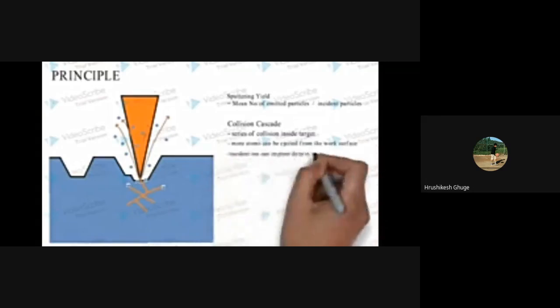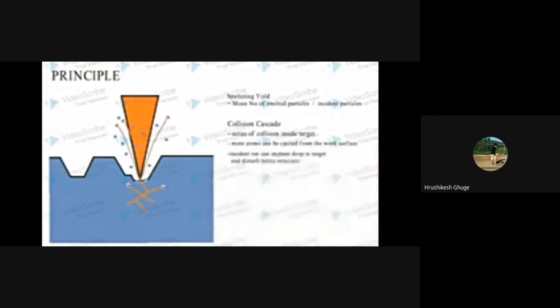And also the incident ion can get implanted in the surface so that it can damage the crystal lattice of the target surface. The cascading effect can be accelerated by using a higher energy incident ion. Cascading effect is accelerated when a higher material removal rate is needed from the ion beam, and though it causes some surface damage, it still yields a higher sputter yield.